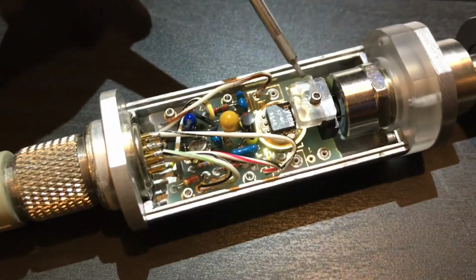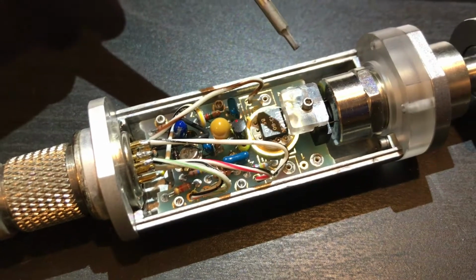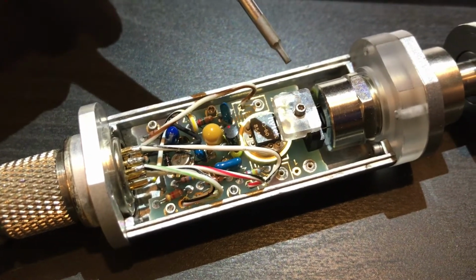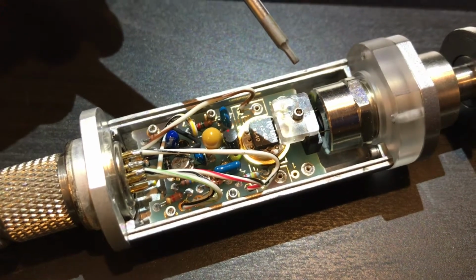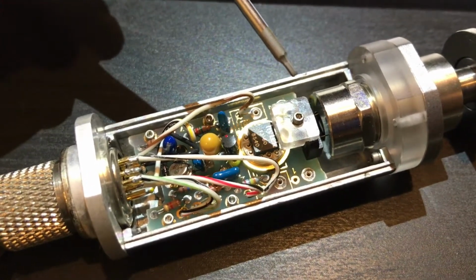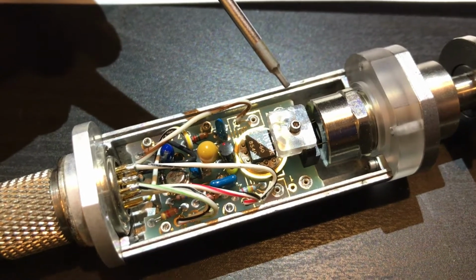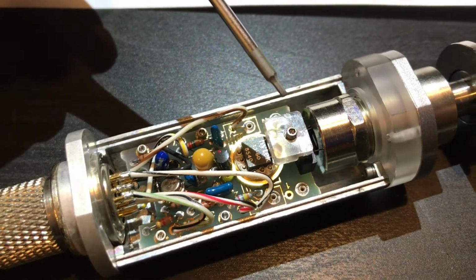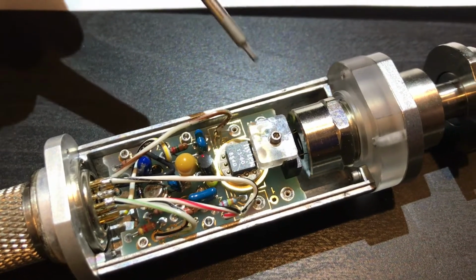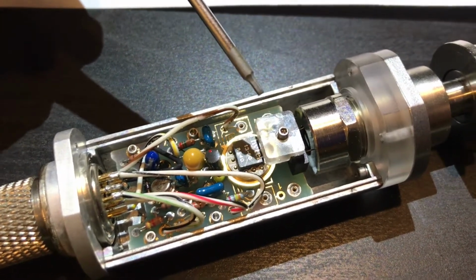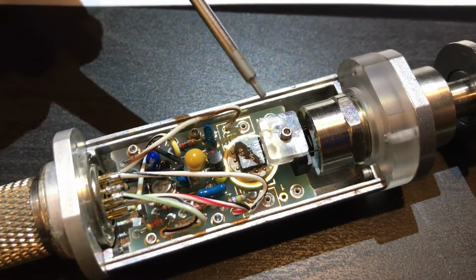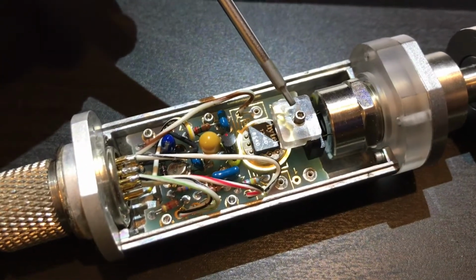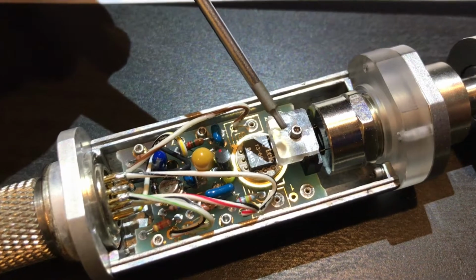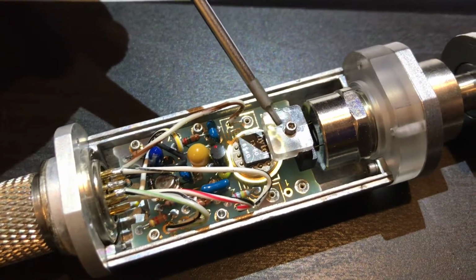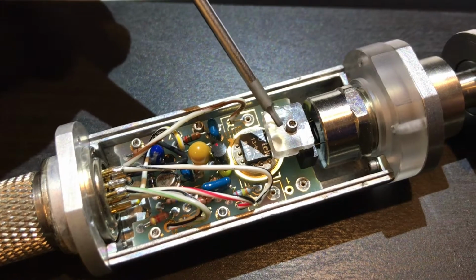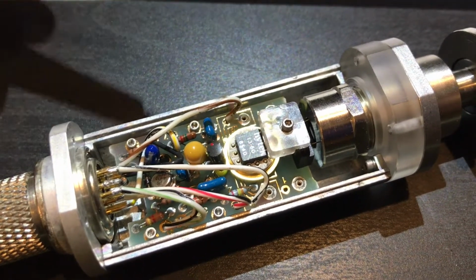Since we're able to read high power signals, that makes sense. But the low power signals, when you're down into the nanovolt regions, would really be affected by just the smallest amount of anything, crud or corrosion down there on those terminals. They would be affected by that signal. And if there's any small amount of bridging across those contacts because of any kind of deposits down there, then that could be causing us to have zero and not be able to zero the sensor.